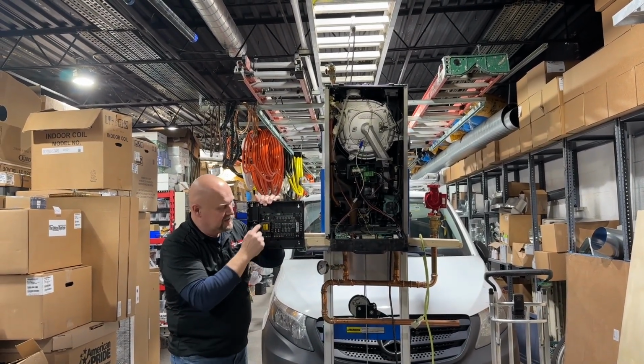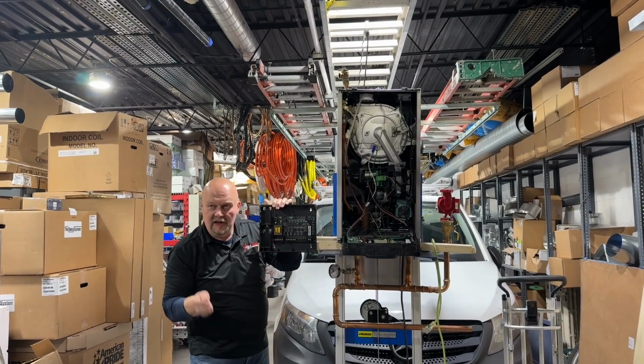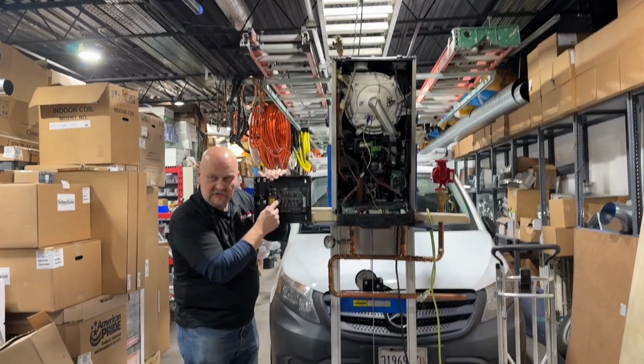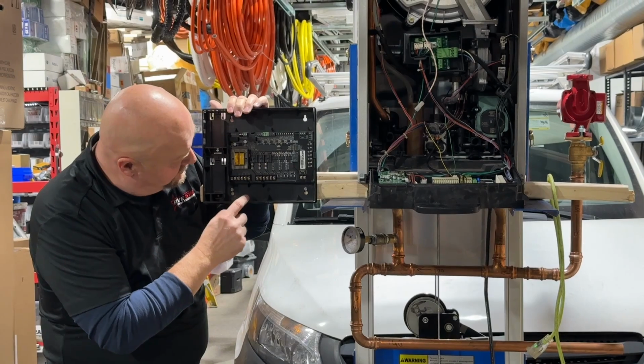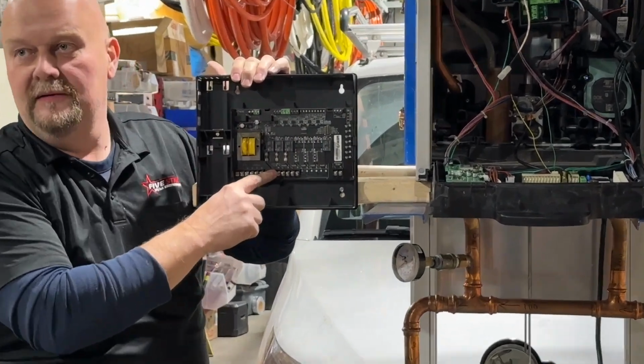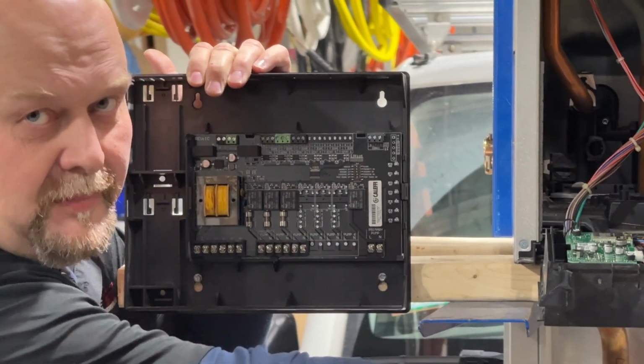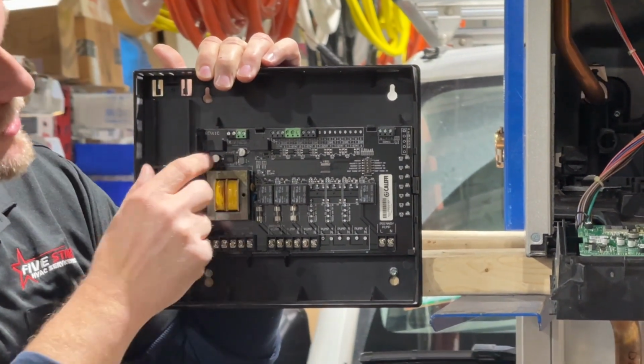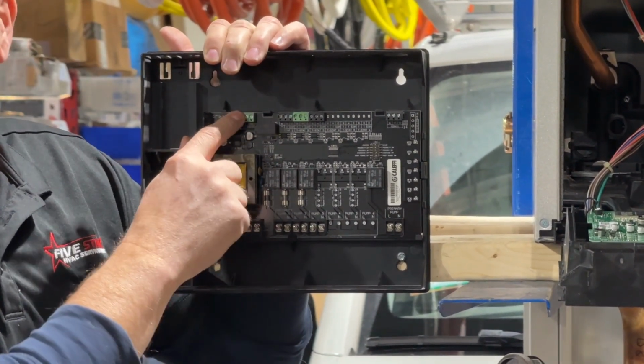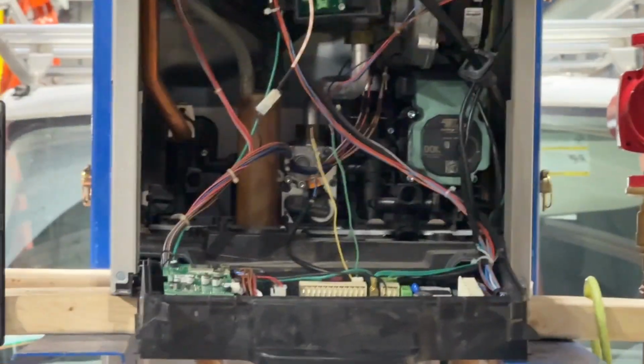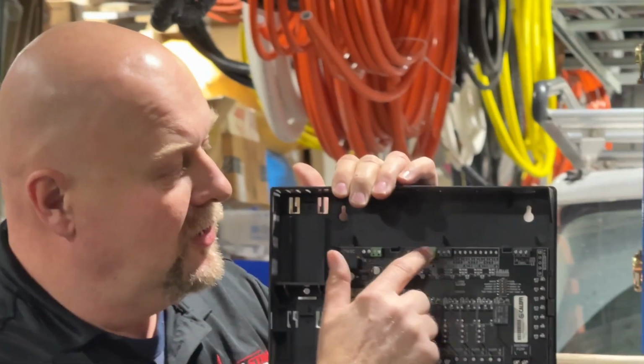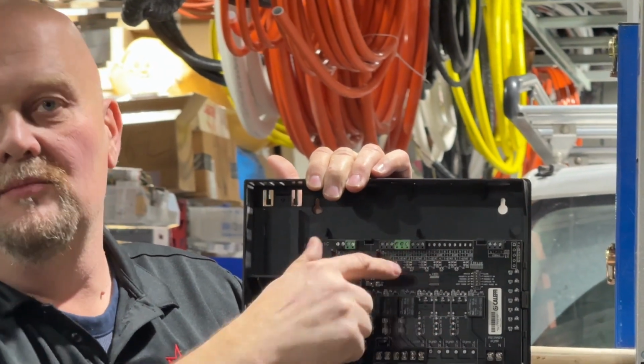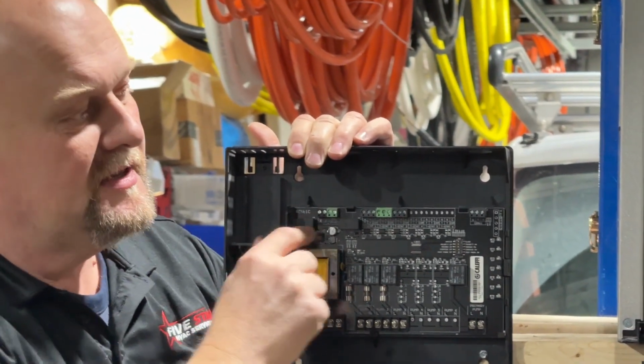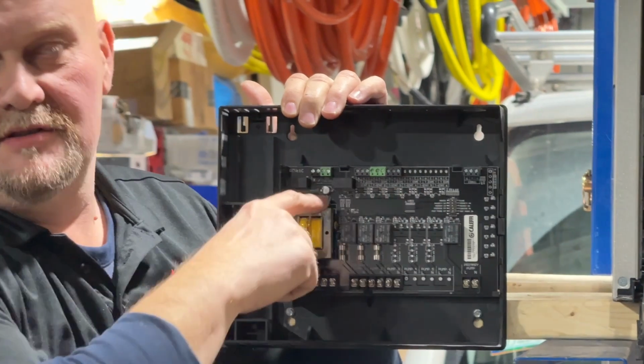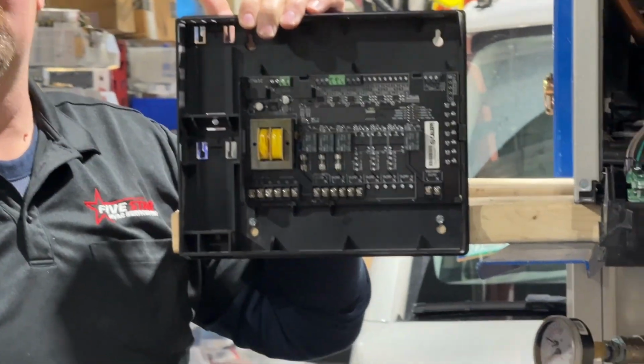And what's gonna happen is this control board here is gonna engage 2 relays. One of these relays right here will send 120 volts to pump 1. That's gonna send power to that pump, let's say, right? And it's also gonna close this relay here so that this can happen and the boiler will come on. If you have more of these zone valves, then more pumps will come on, but at the same time, the boiler also comes on because these are all piped and connected parallel.